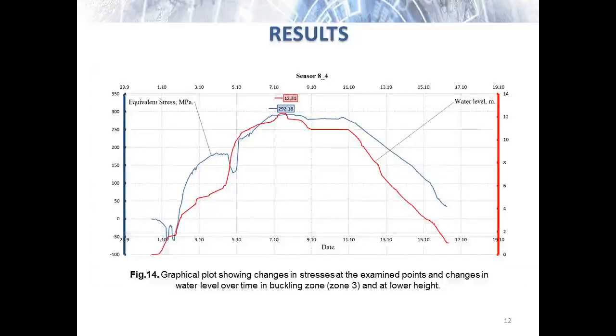At the beginning of the experiment, the jump signals were registered at a height of more than 5 meters. This is due to the fact that the examined zones of the tank took an equilibrium shape under hydrostatic pressure. In the mid-stage of the experiment, the strain values in these joints were normalized, and the absence of sharp increments was registered.